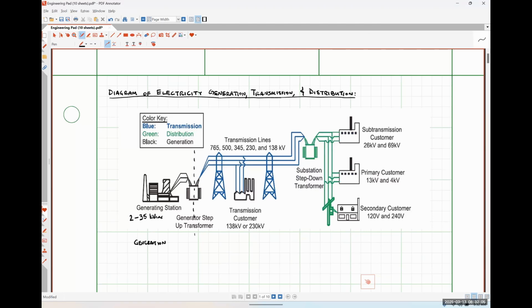Essentially, if you step up a voltage from, say, 10 kilovolts to 500 kilovolts, that's an increase of about 50 times—10 times 50 is 500, if my mental math is correct. Now if you step up the voltage by a factor of 50, you actually step down the current by that same factor. So when we transmit power over long distances using transmission lines, we try to do it at as high a voltage as possible so that we're transmitting at as low a current as possible. Anybody have any ideas why we might want to transmit power using very low currents?